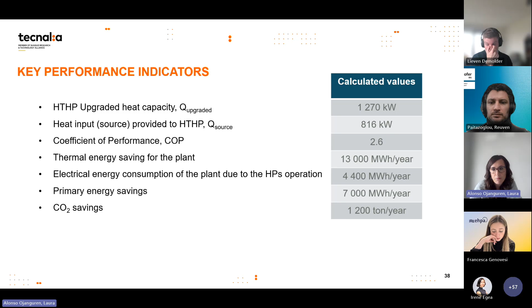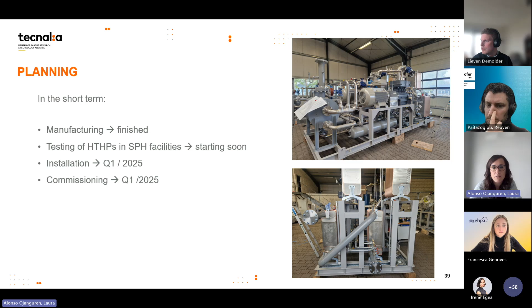Regarding the timing or planning for this project, in the short term, the manufacturing of the high temperature heat pumps is finished - you can see some pictures here. The testing of the high temperature heat pumps in SPH facilities will be starting soon, and right after the testing, the machines will be sent to the plant, with installation and commissioning taking place in the first quarter of 2025. So really soon we will have, as said, the first high temperature heat pump producing steam running in Spain.